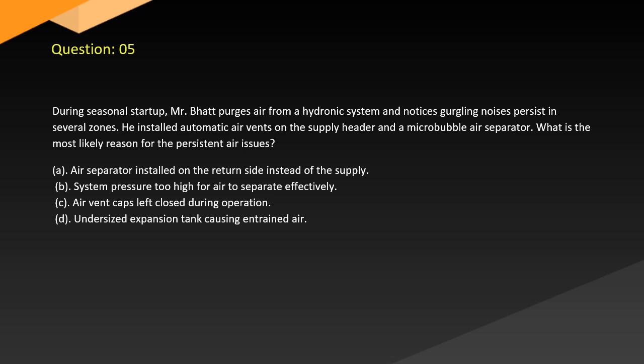A. Air separator installed on the return side instead of the supply. B. System pressure too high for air to separate effectively. C. Air vent caps left closed during operation. D. Undersized expansion tank causing entrained air.